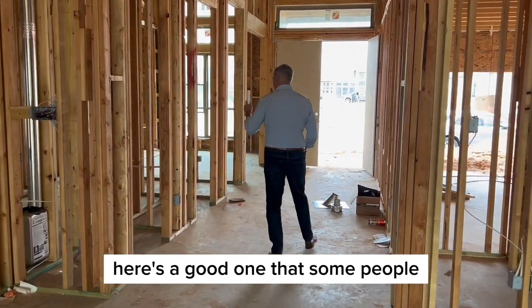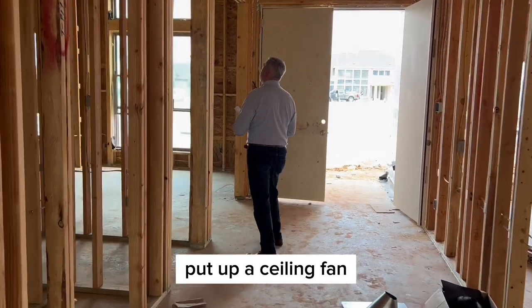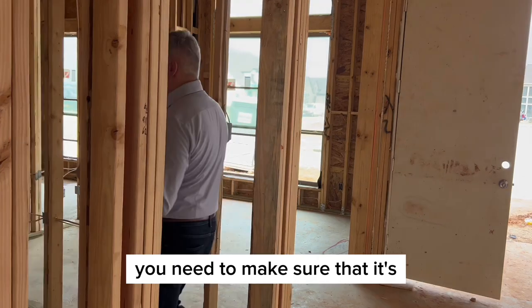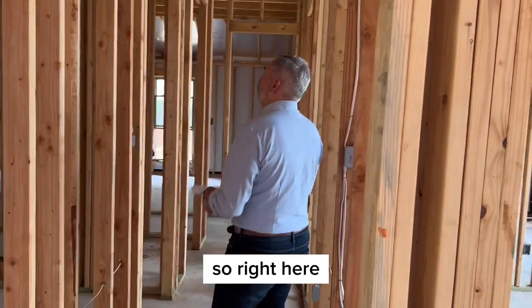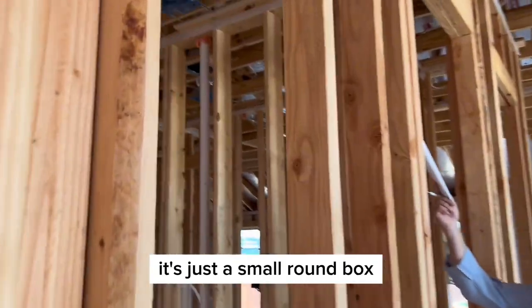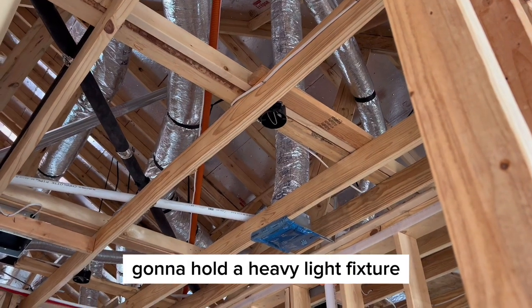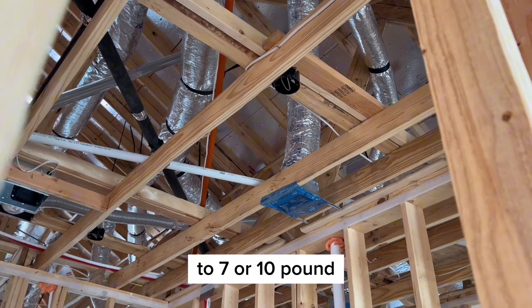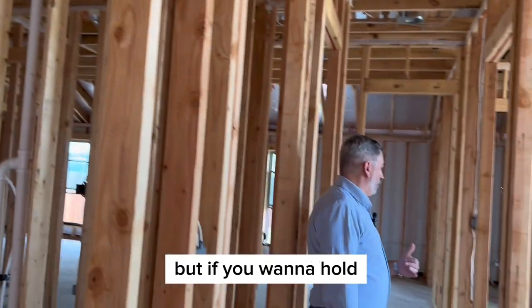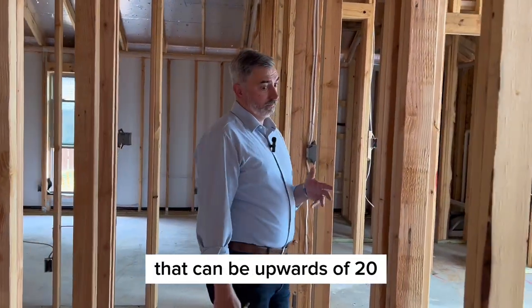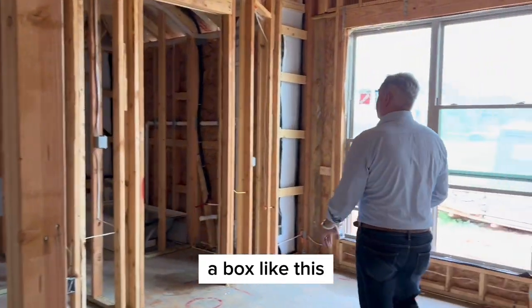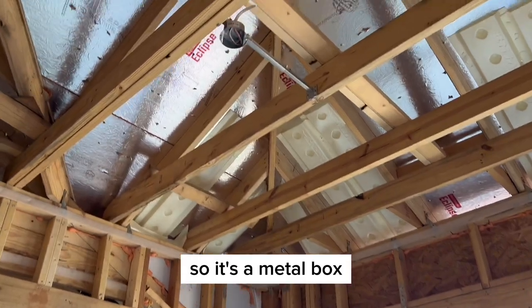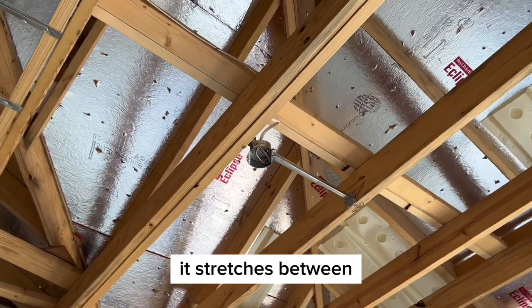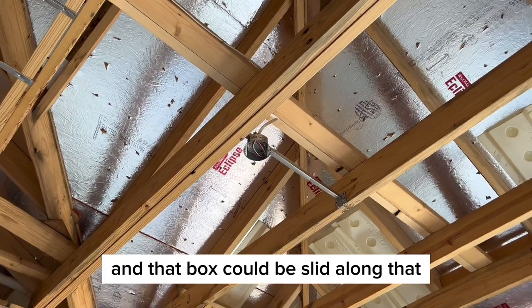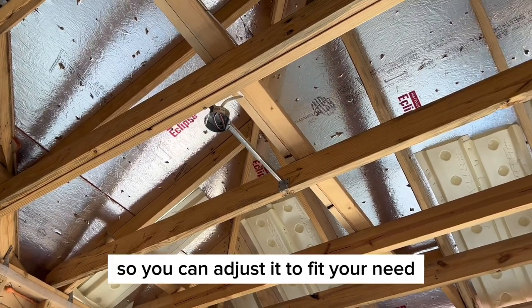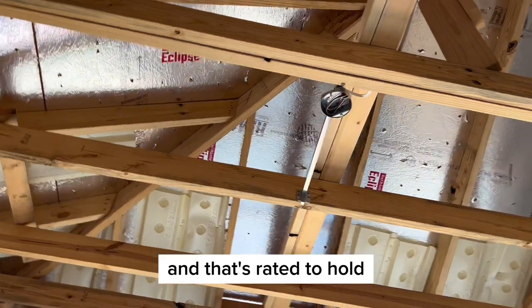Here's something some people don't realize: when you want to put up a ceiling fan or hang a light fixture, you need to make sure the box can hold it. Right here you'll see a light fixture in the ceiling—it's just a small round box. That's not going to hold a heavy light fixture, just a 2 to 7, maybe 10 pound ceiling mount fixture. But if you want to hold a ceiling fan, which can be upwards of 20 to 30 pounds, you need a box like this—a tension box. It's metal, not plastic, and stretches between the framing members. The box can be slid along that metal bar to adjust it to fit your need, and it's rated to hold ceiling fans or heavier fixtures.